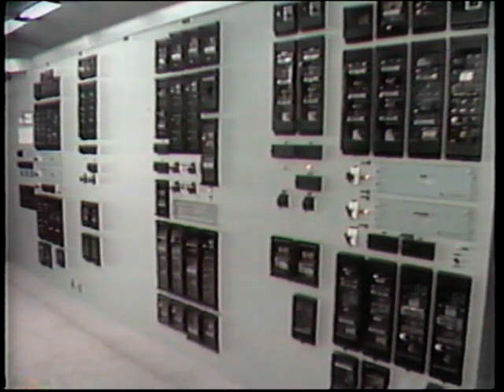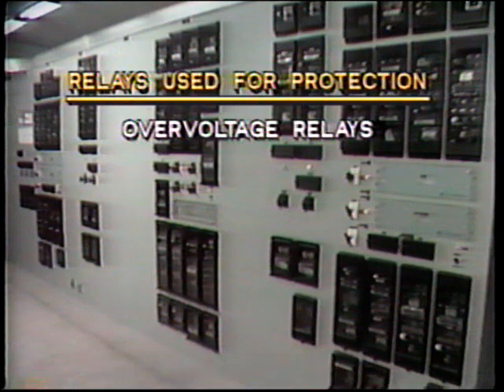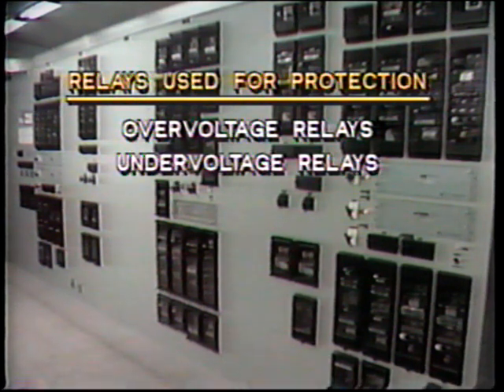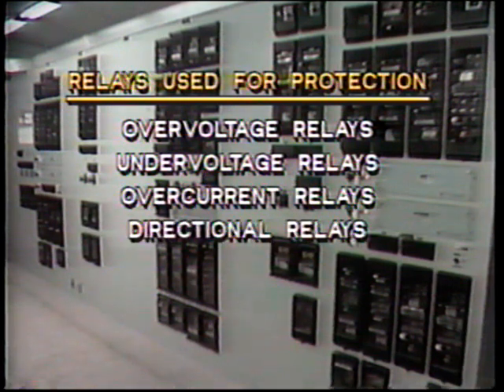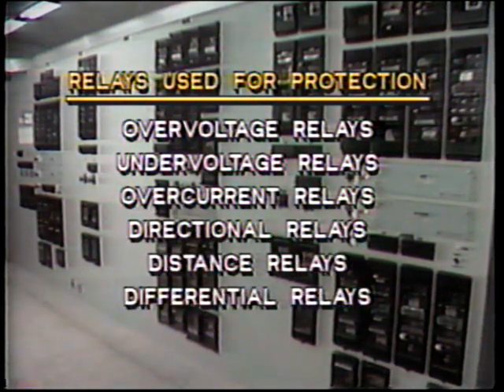Up to now, we've been talking about protective relays. In fact, the whole thrust of this video program is in the application of protective relays. The most common types of relays used for protection are over-voltage relays, under-voltage relays, over-current relays, directional relays, distance relays, differential relays, and I'm sure you can think of many others. We'll be talking about these types of relays in the next videotape and as we proceed on through the series. However, there are other relays installed on the system which do not cause tripping of breakers for protection. But a knowledge of these relays is important in operating and maintaining the power system.